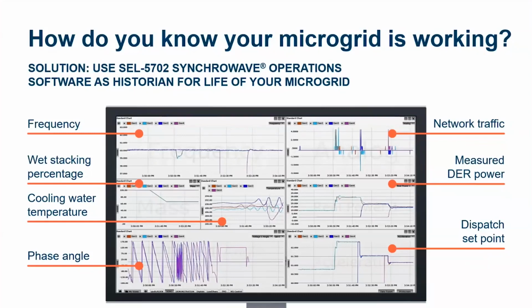So we see phase angles recorded for all time of the microgrid per IEEE 2030.8 standards. You have to record all of these events for the history of the microgrid to meet that standard. We do with this software. Here we record all of the phase angles across the breakers of every synchronization event. You see dispatch set points from the microgrid controller. You see measured power from all your DERs. Here, there, as these generators turn on and off, we see the dispatch changing. And we can also see network traffic. We can see attacks. This is your preferred dashboard for your microgrid controller.